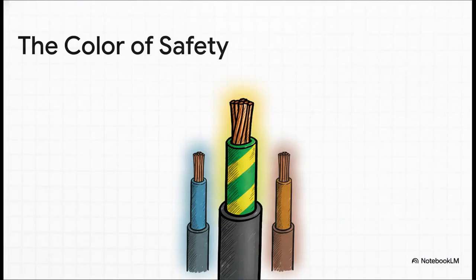First things first, identification is absolutely critical, and the standard is incredibly strict about this. The protective earth wire has to be colored with a green and yellow combination, and that color code can never be used for any other wire. It's a universal signal for safety.